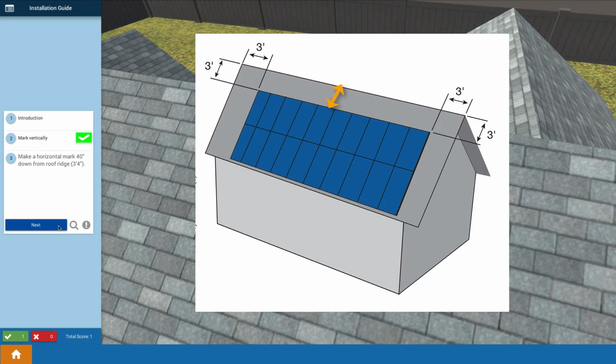And realize that this is a minimum requirement. You need 3 feet or more. In our lesson, we actually say go the 3 feet and then add about 4 inches more just for safety, to make sure there's no question when you get inspected that you're at least that 3 feet or 36 inches down. But you can make it more depending on the size of the roof.